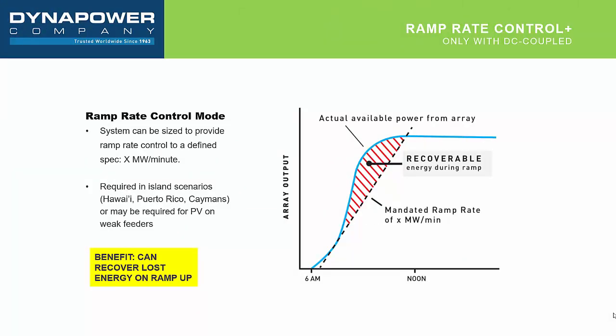A similar phenomenon applies with ramp rate control, and we're referring to this as ramp rate control plus. Now, ramp rate control itself is well understood, and we can use AC coupled or DC coupled storage for basic ramp rate control. What we mean by ramp rate control plus is that if you are in a situation where your ramp rate up, that is your system is coming on, but you are limited in the speed with which you can ramp up your array, you're essentially clipping your PV array output. There's energy to be harvested there. And again, when you have a DC coupled system, you can capture that energy. And that's shown here in the graph to the right.